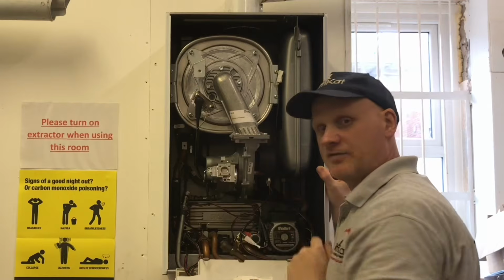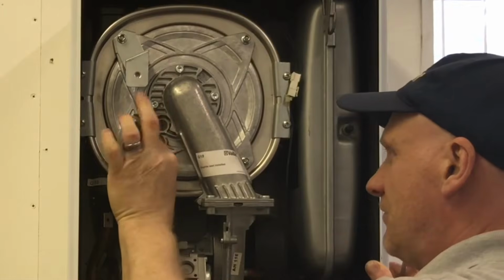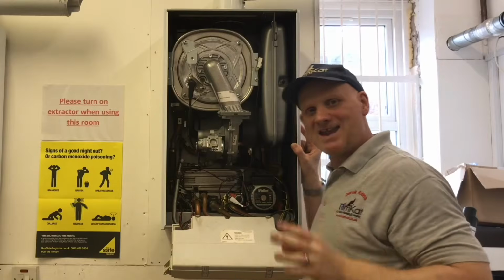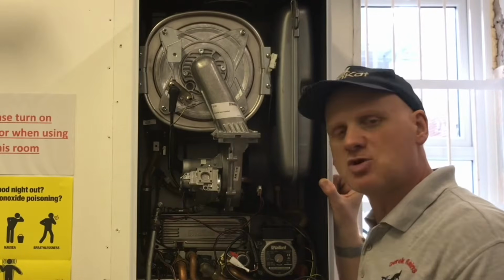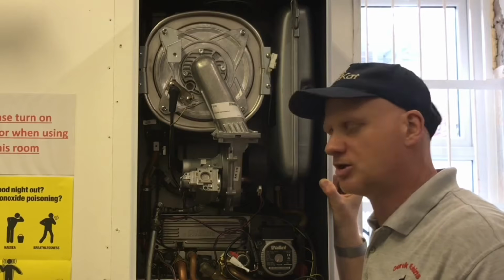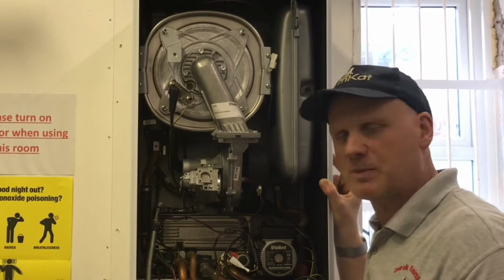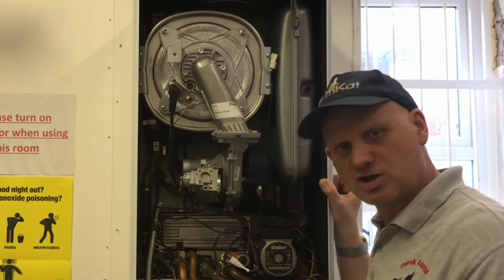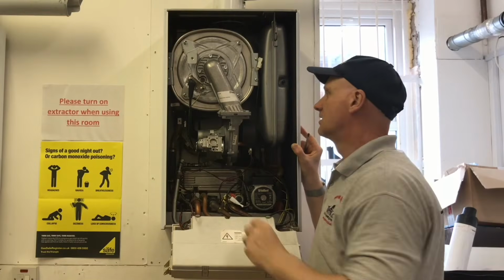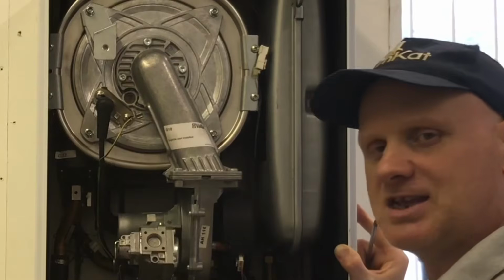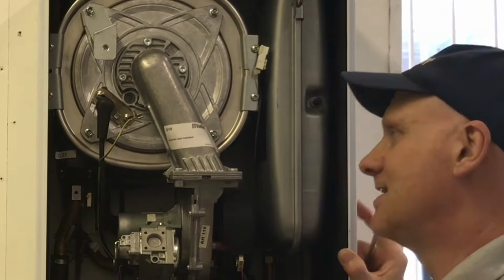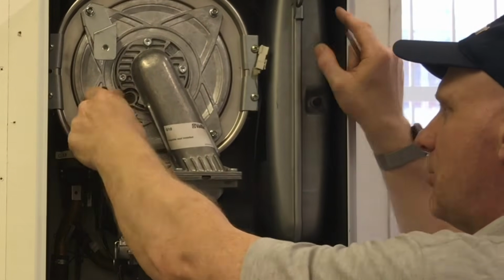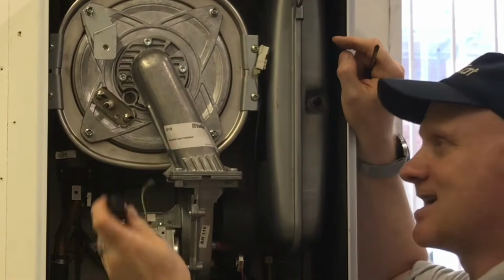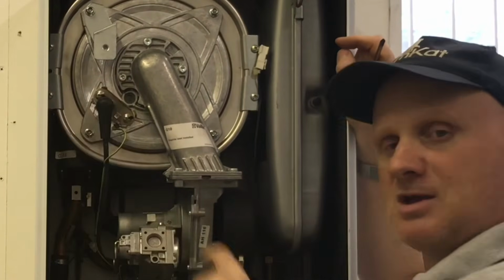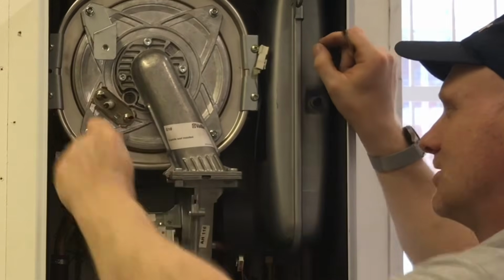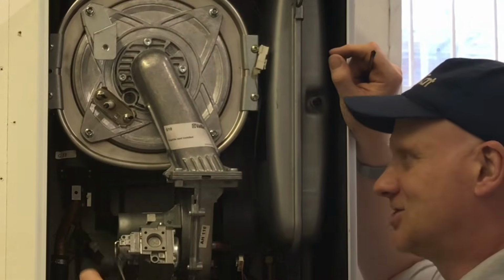What I need to do now is take off the HT lead. Now, earth wire comes off first, but remember, before you do any work inside a boiler whatsoever, you must follow the safe isolation procedure and use your non-contact voltage indicator pen to make sure this isn't live before you touch it. It could save your life. Okay, now, earth's off, HT lead. Now, depending on how old this boiler is, these can become very, very brittle. So when you're pulling them off, they can actually break inside, but the worst one is when you're putting them back on, because they're very, very stiff to get on and off. So just watch out for that. You could actually end up breaking the HT lead on that.